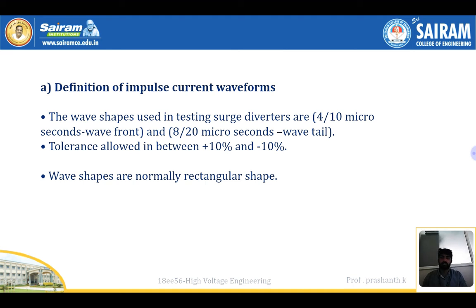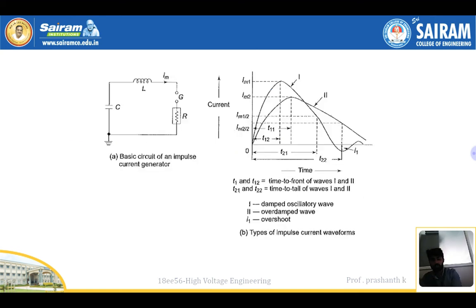Impulse current waveform definition. The wave shapes used for testing surge diverters are 4 by 10 microseconds, wavefront, and 8 by 20 microseconds, wavetail. Tolerance allowed is plus 10 percent to minus 10 percent. Wave shapes are normally rectangular or similar shapes. The basic circuit of an impulse current generator has capacitance C, inductance L, and resistance R. T1 and T2 are the times to front and the times to tail of the wave. The first is a damped oscillatory wave, the second is an overdamped wave, and the third is an overshoot.